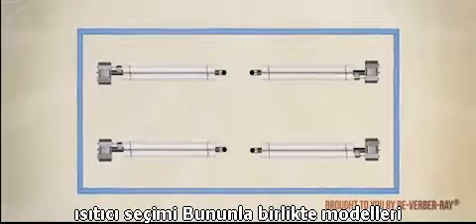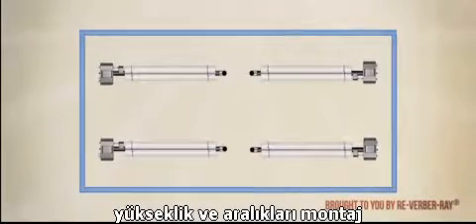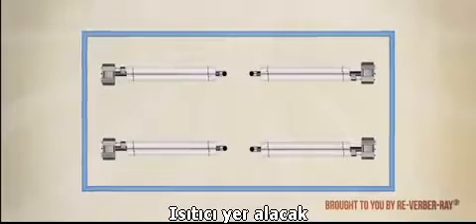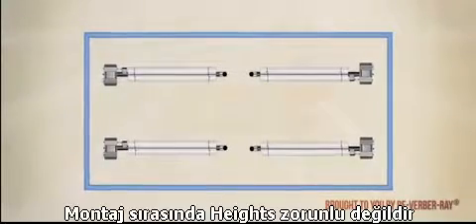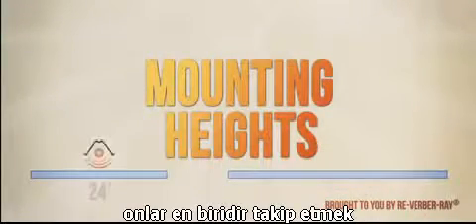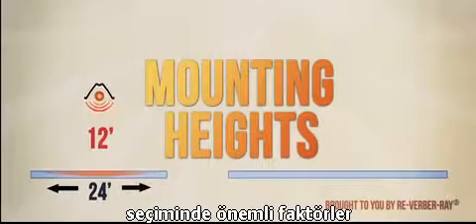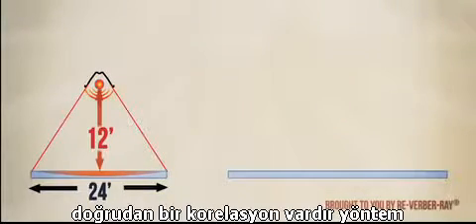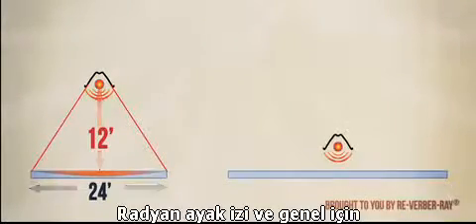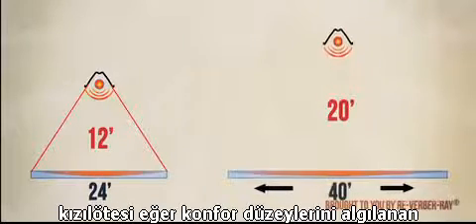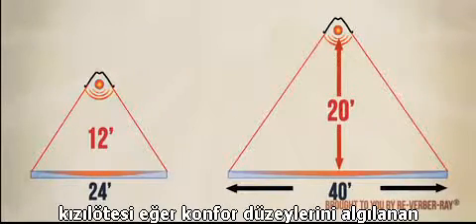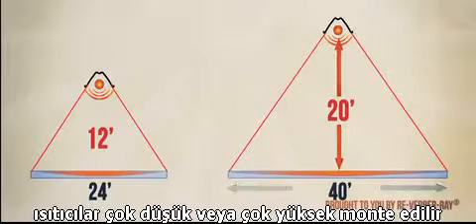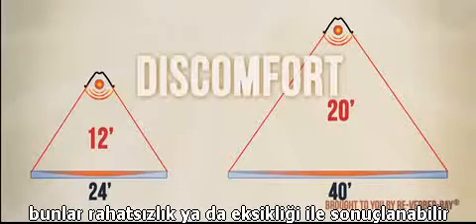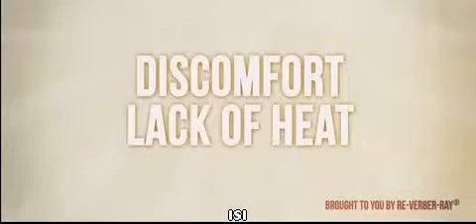However, heater selection is generally based on the available mounting heights and clearances where the heater will be located. While mounting heights are not mandatory to follow, they are one of the most important factors in the selection process as they are directly correlated to the radiant footprint and overall perceived comfort levels. If infrared heaters are mounted too low or too high, they may result in discomfort or a lack of heat.